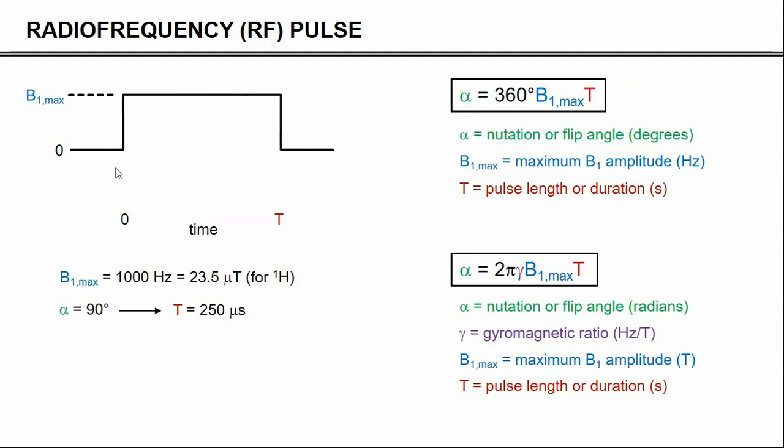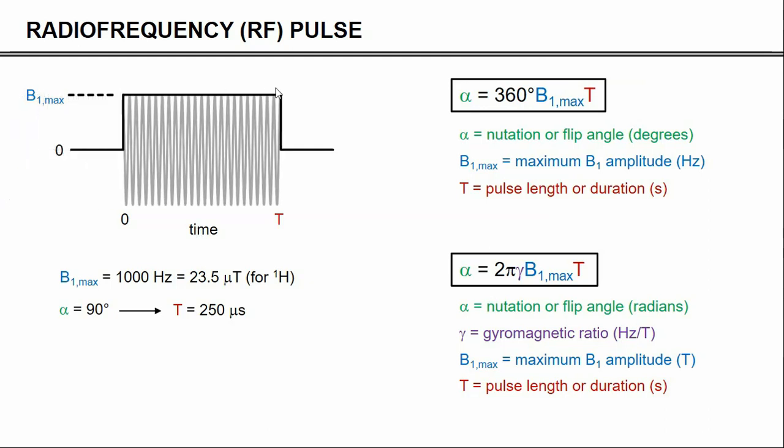Now, before we move on, it is important to realize that this black line is only the envelope function of the square pulse. The square pulse itself is, of course, applied at the Larmor frequency, and the Larmor frequency is typically between a few megahertz to several hundred megahertz. So there is always a frequency modulation that is part of this. But most publications only show the envelope function, shown in black. But always be aware that it is actually a high-frequency RF pulse.